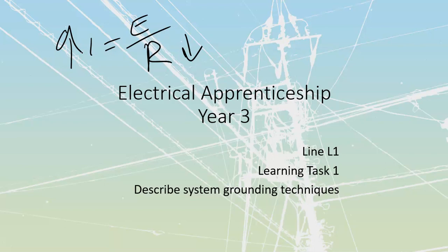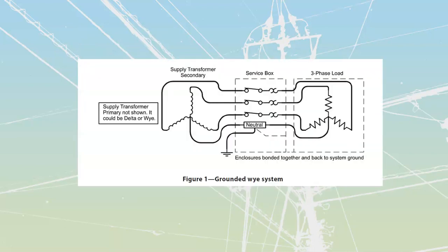Because of this, we're going to once again monitor our system. If we have a single fault on a delta system, nothing happens. If we have multiple faults on a delta system on different lines, we're going to get massive amounts of current that will flow. So those are the 3 main that we're going to look at. We're going to start by taking a look at our solidly grounded system. And the first one we will look at is going to be a Y system.